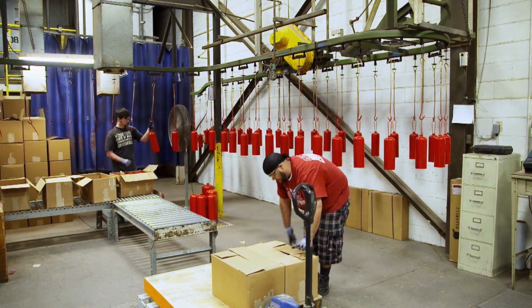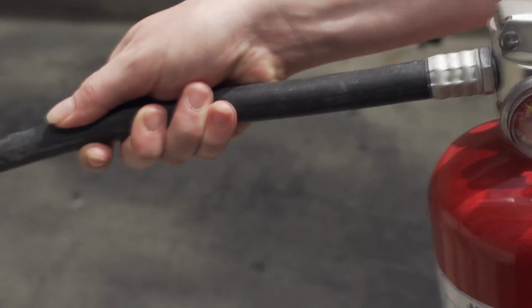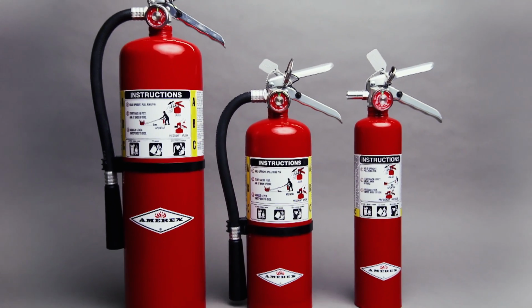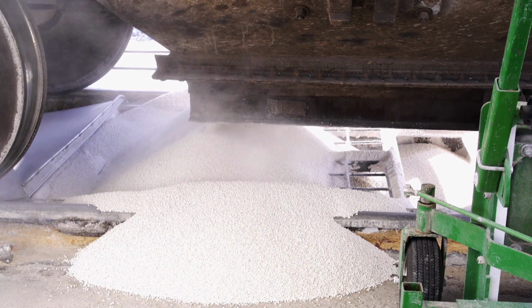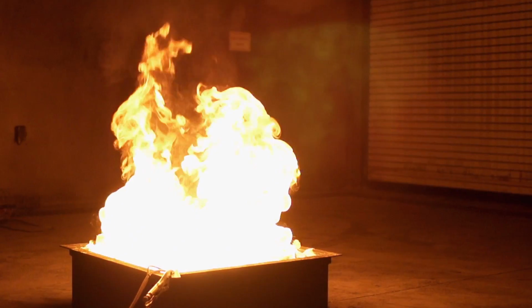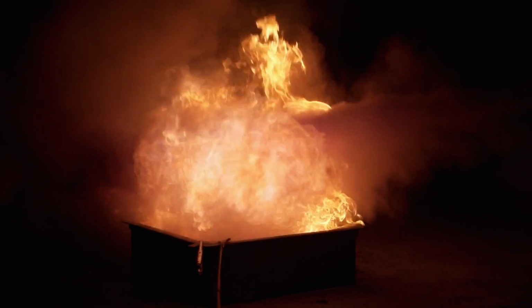Ready for filling, the content today is a far cry from the early days of the water extinguisher. Just like your smartphones change literally day to day, that's how hazards and techniques for suppressing fires change on a daily basis. Today, dry chemical compounds conquer just about any household combustibles. A vast majority of the chemical compounds in the dry powder are monoammonium phosphate and ammonium sulfate. Those are common chemicals found in most crop fertilizers. It creates a coating over the surfaces and it effectively cuts off the oxygen flow to the fire itself.